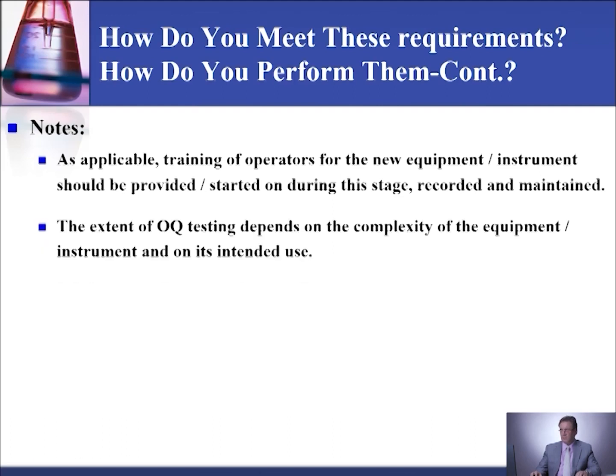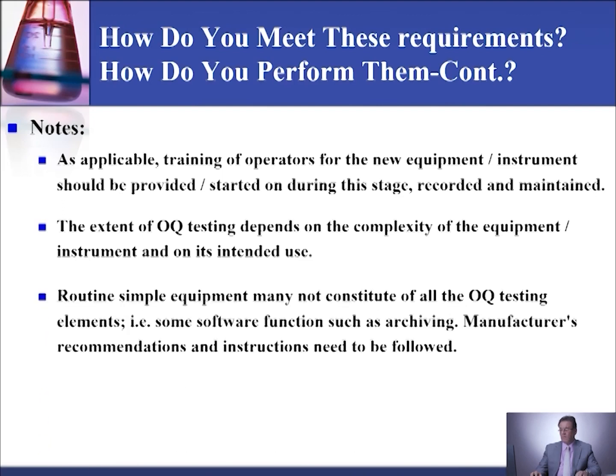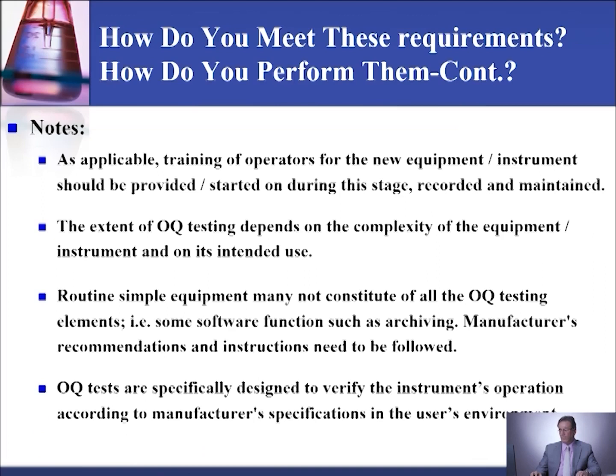and recorded and maintained. The extent of OQ testing depends on the complexity of the equipment or instrument, and on its intended use. Routine, simple equipment may not include all of the OQ testing elements I'm going to mention to you, or some software functions, such as archiving, for example. Manufacturer recommendations and instructions need to be followed. OQ tests are specifically designed to verify the instrument operation according to manufacturer specification in the user's environment.